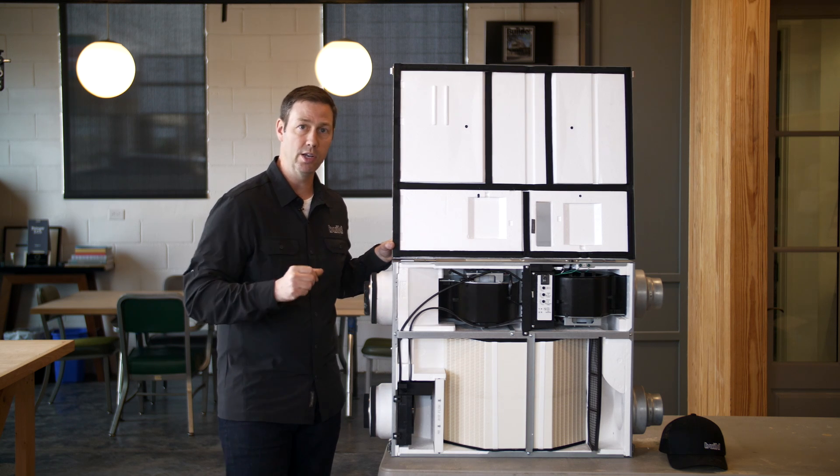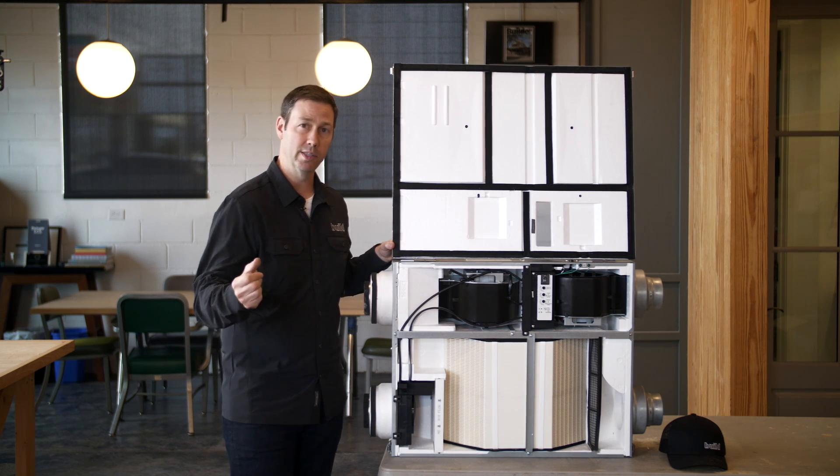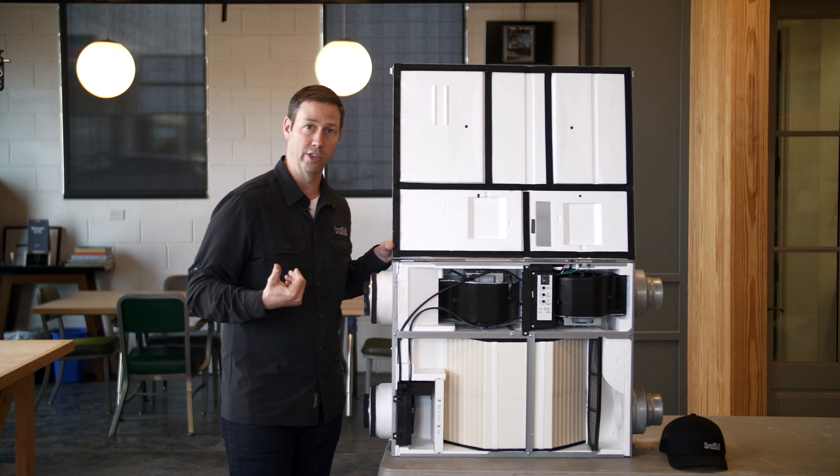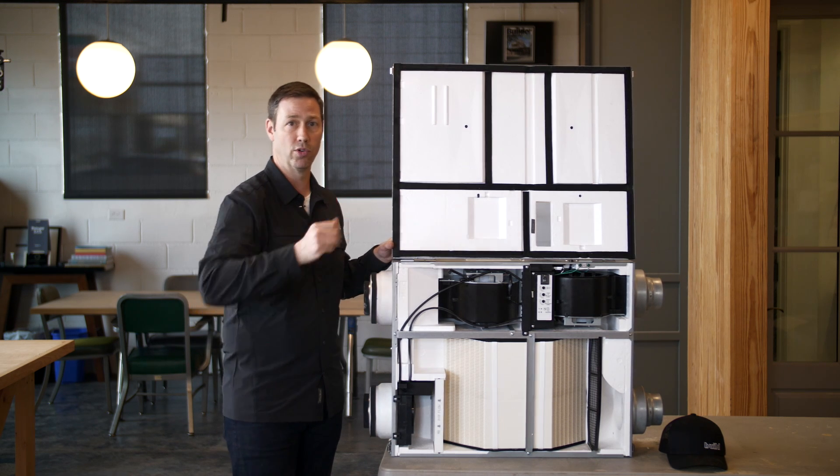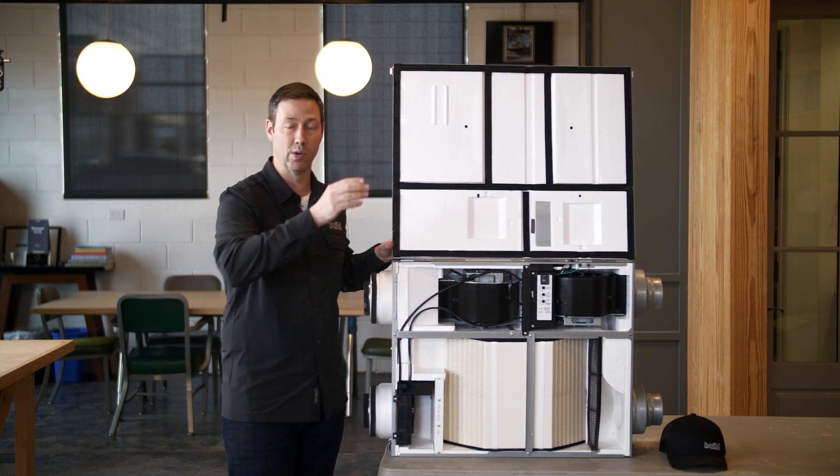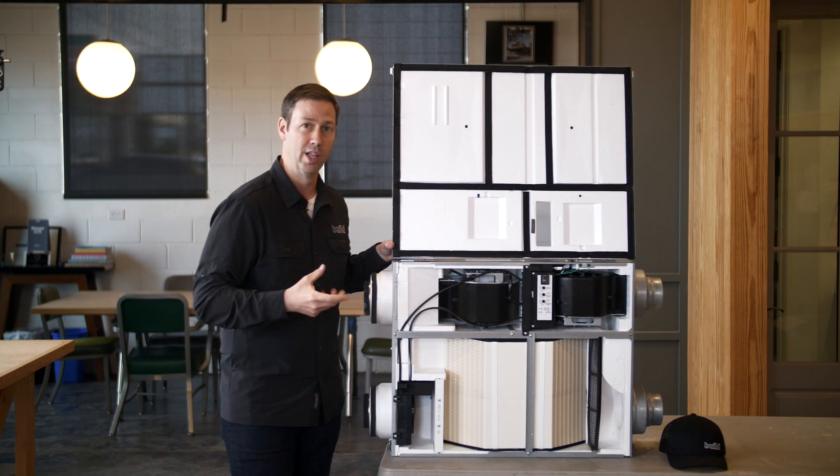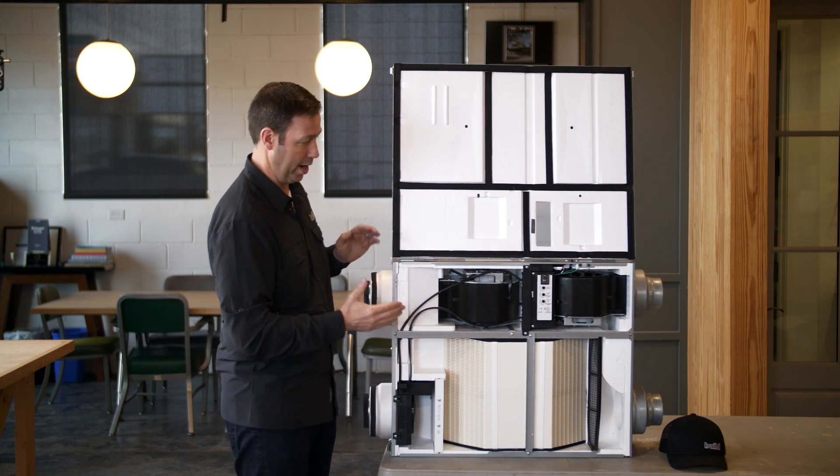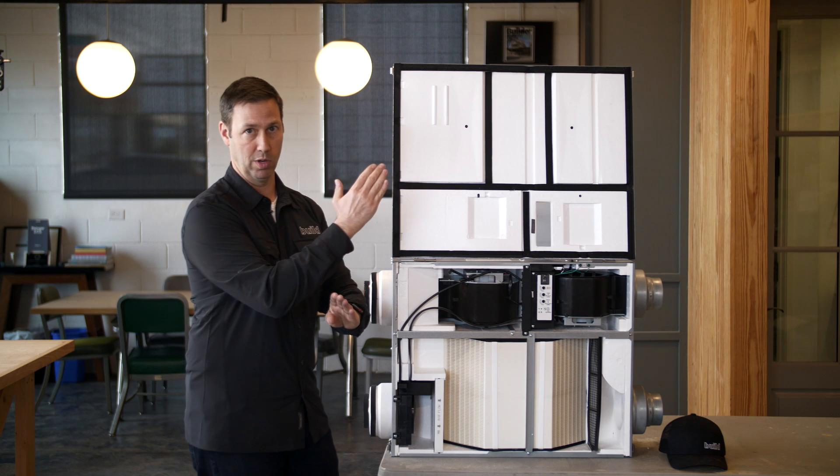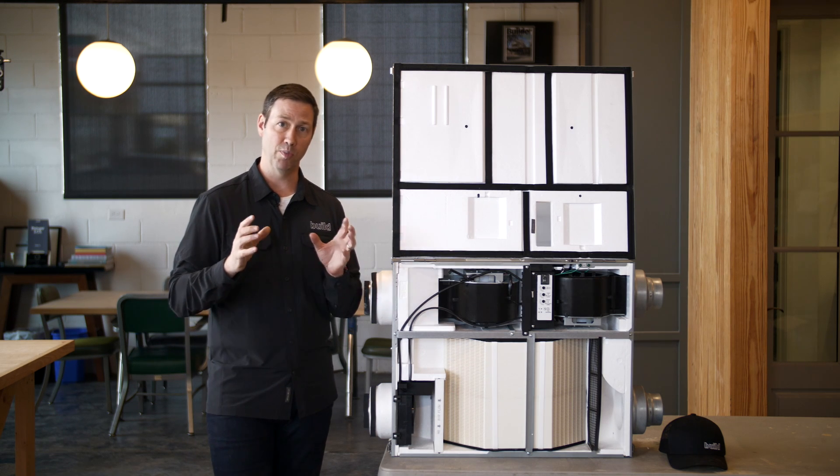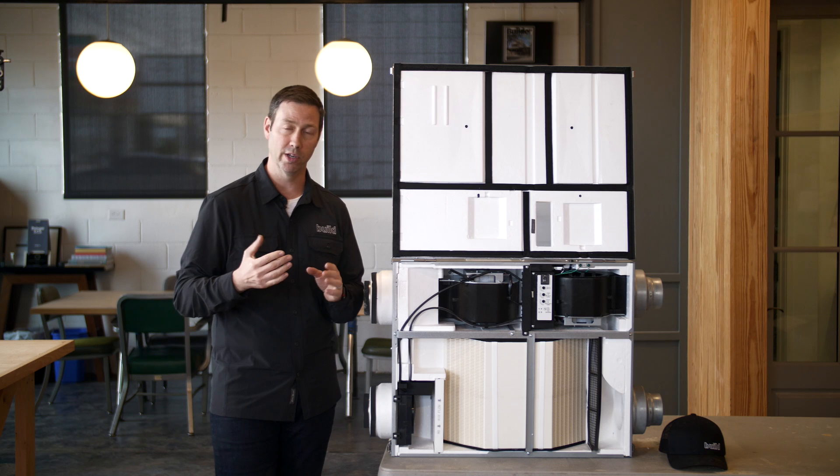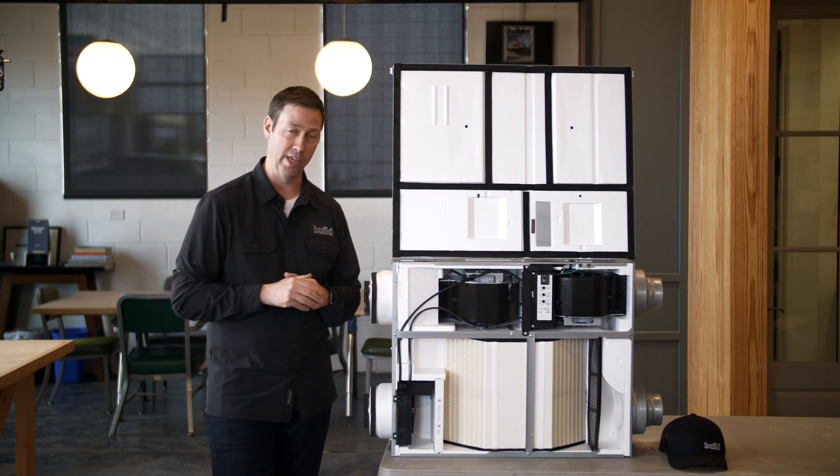Now an HRV stands for heat recovery ventilator. The idea is when you're bringing in fresh air in the wintertime, especially if you're in the cold north, it might be zero degrees outside. You don't want to drop zero degree air into your bedroom as fresh air. Instead, you want to warm that air with the outgoing stream of air. That's why they call it a heat recovery ventilator. There's less of a penalty as you bring that cold air in because it's going to be warmed up by the outgoing stream.